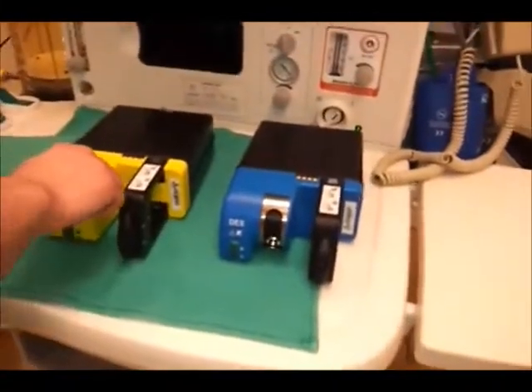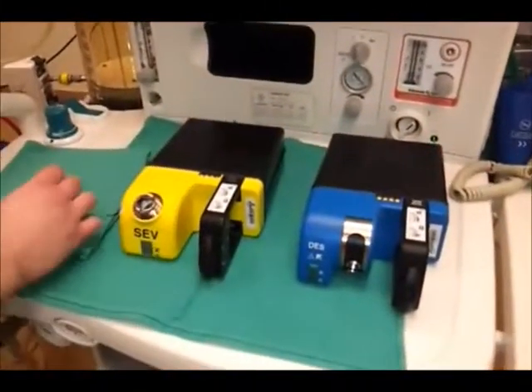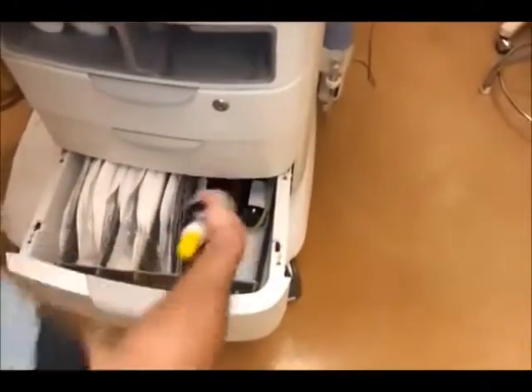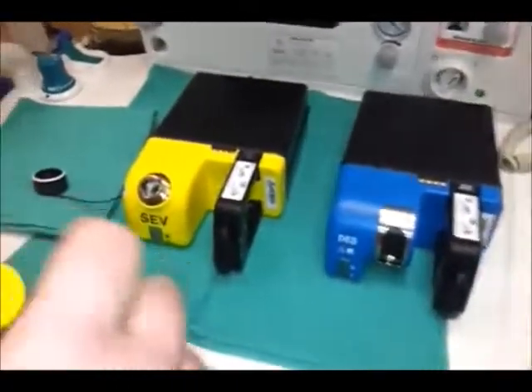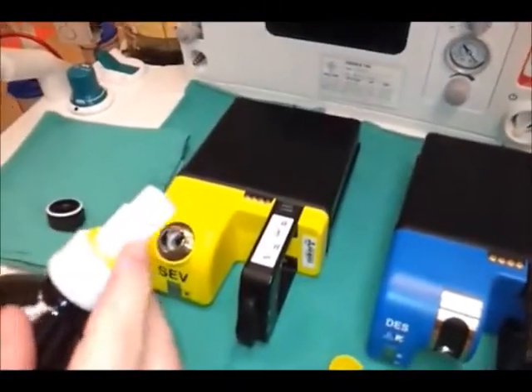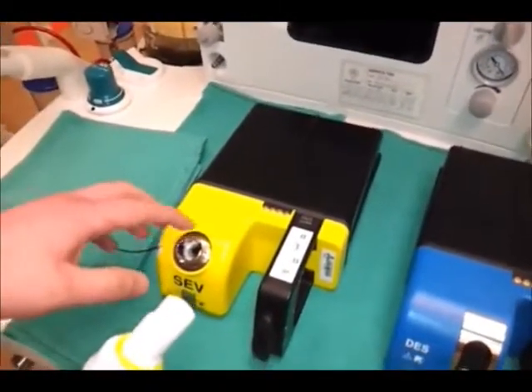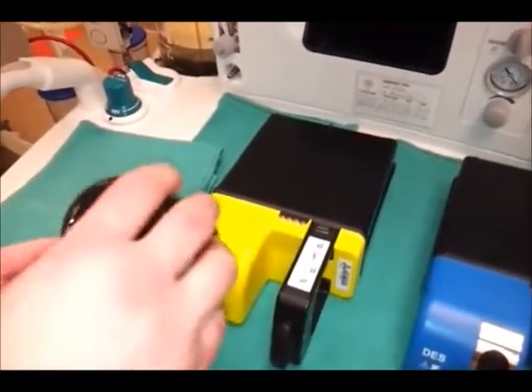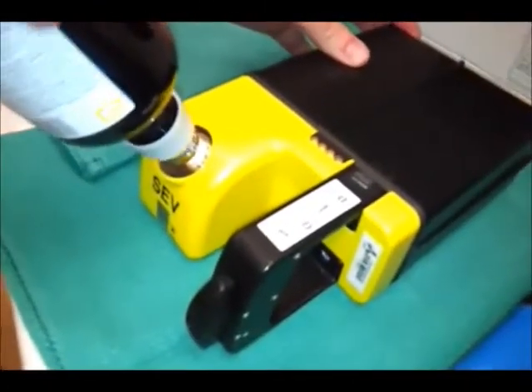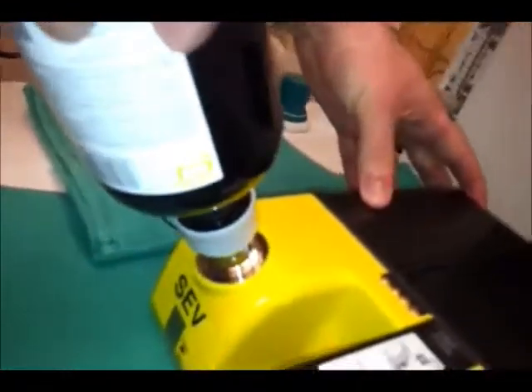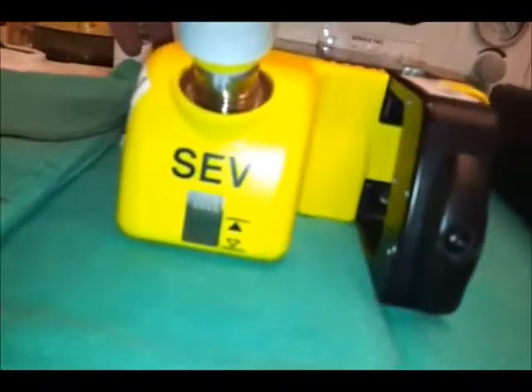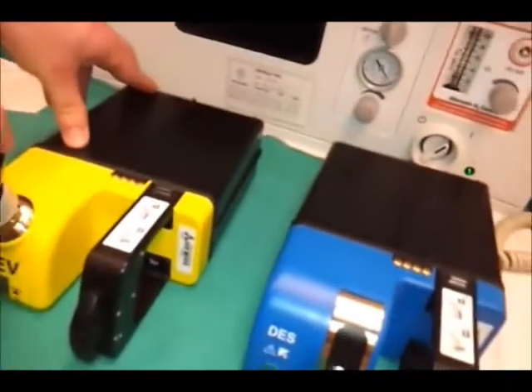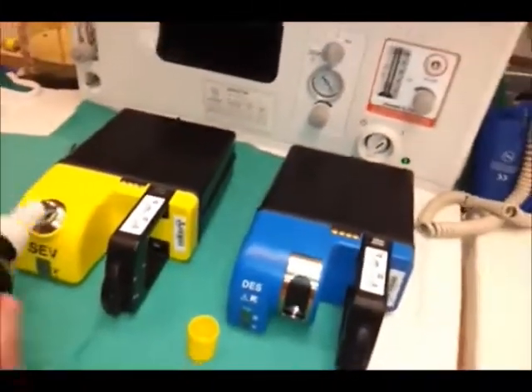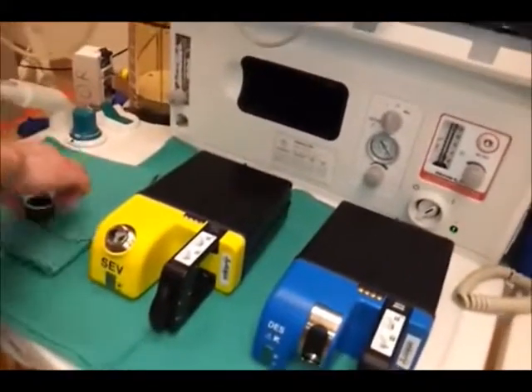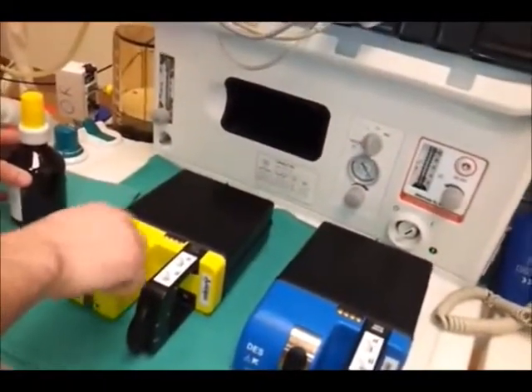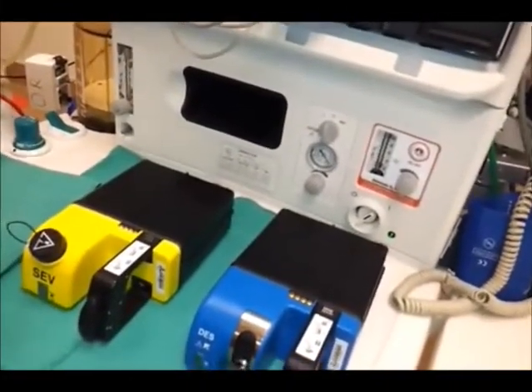These are full, but I'll just show you how you would fill them if you had to. So you take the cap off that and get the gas out of the bottom drawer here. And you can see that there's kind of a little key on the bottle, and you just want to line that up with the key on the cartridge. So you just push it in, and you'll hear bubbles coming up through the bottle, and you want to watch the level and make sure it's not overfilling. And then when the bubbles are done coming up, you just take it out, put the cap back on the bottle, put the cap back on the cartridge, and then you're good to go.